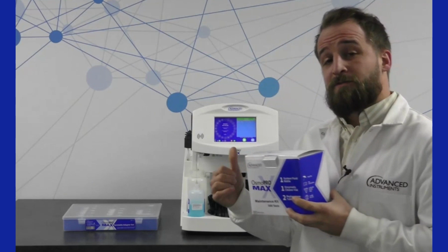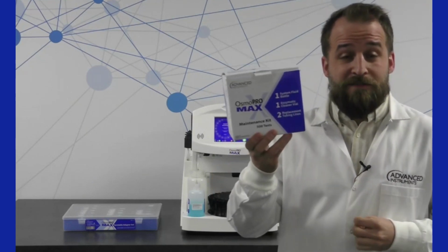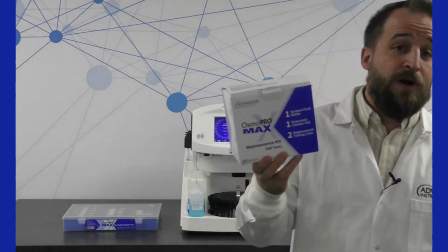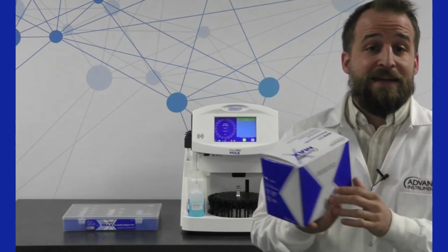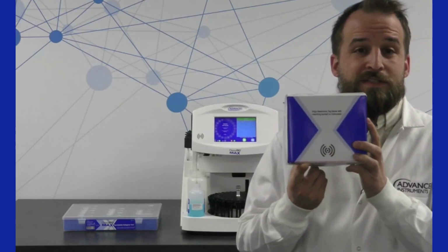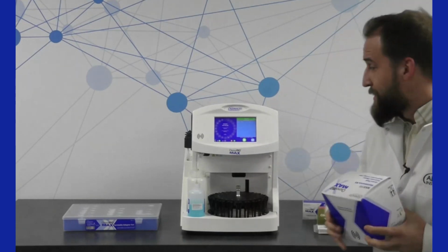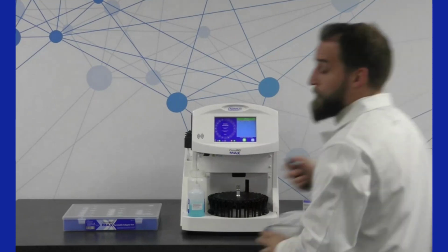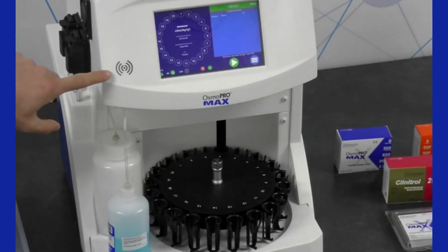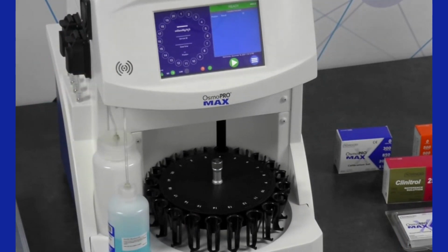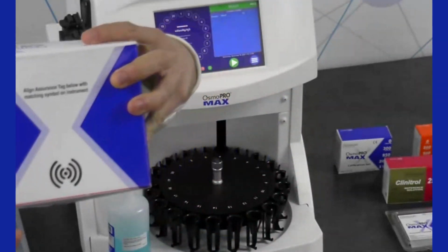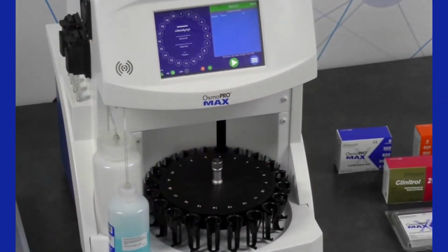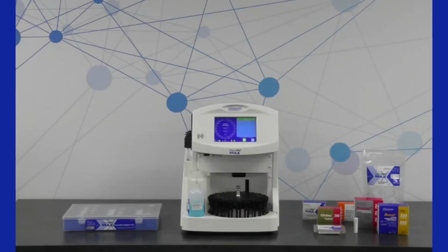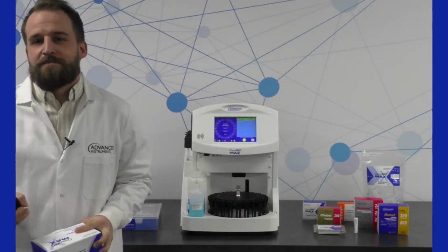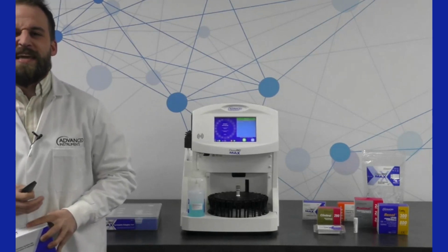There's actually a counter in the software, I'll show you that later, that resets each time you perform this 500 test maintenance and indicates how close you are to needing to perform the Max 500 kit maintenance again. Something that you'll see with this consumable, and another consumable that I'll show you, is this RFID tag. That RFID tag is compatible with this RFID scanner located on the front of the instrument. So when you want to initiate your 500 test maintenance, you would simply take the kit and hold this RFID symbol up to the RFID reader on the instrument, and it would initiate a step-by-step instructional video showing you exactly what steps to take every step of the way. So it takes the guesswork out of performing things like that.